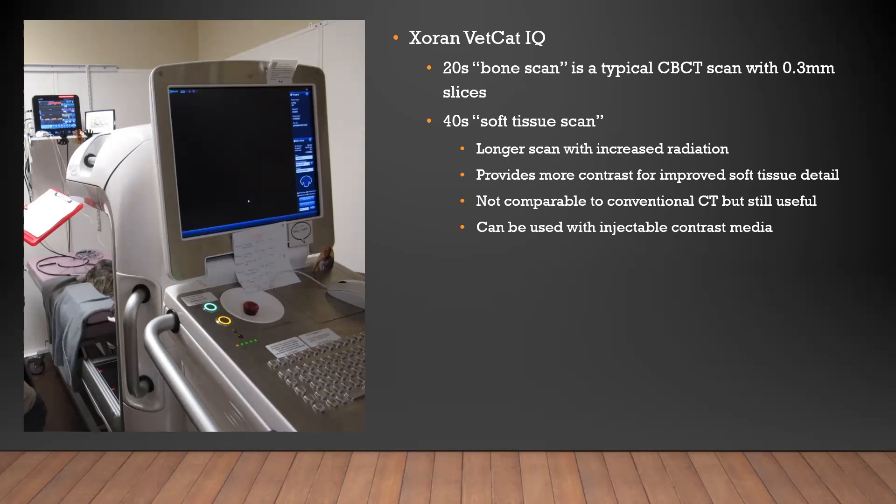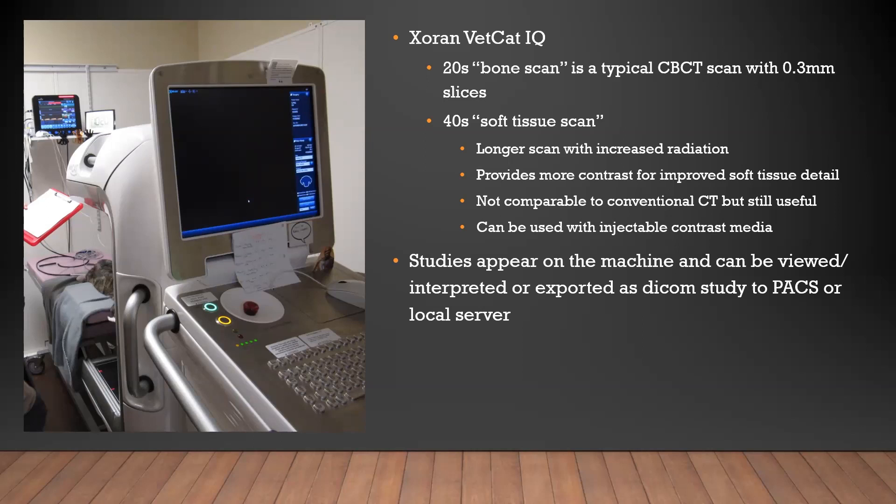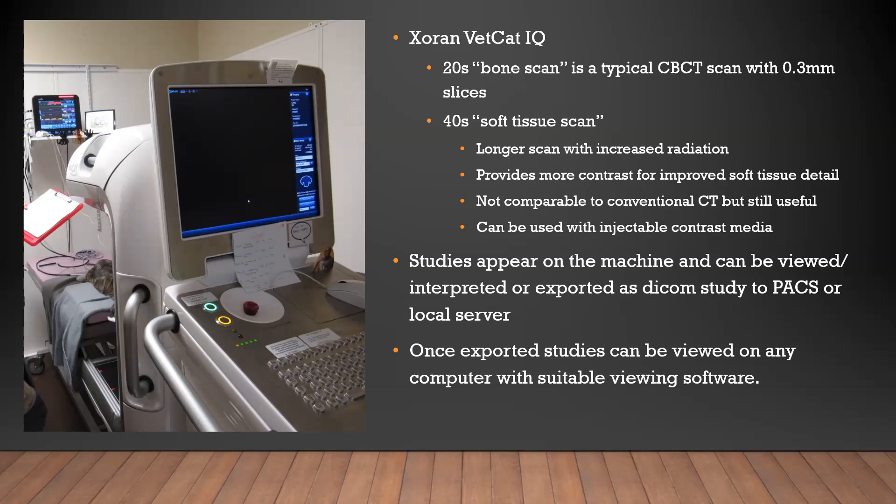Every machine comes with its own intrinsic software for viewing and interpretation. The scan or study, once created, can be exported either as a DICOM or in Xoran's own proprietary file format. You can store it on the machine or export it into your PACS system as a DICOM and use any DICOM viewer. That's useful because these machines are really fast but interpretation could take time. In our offices we usually have at least three tables, so we need to get those scans exported and look at them on a different workstation to maximize our use of this piece of equipment.